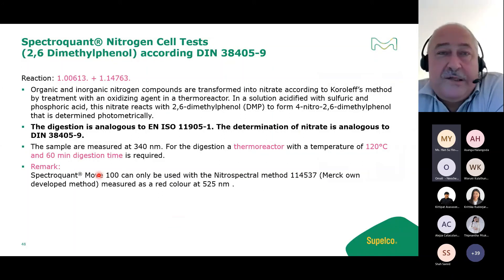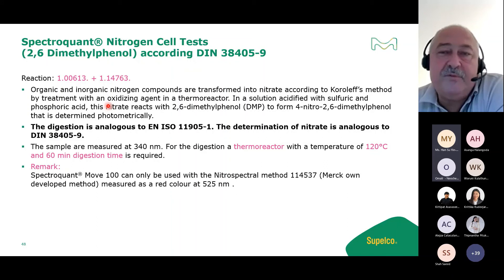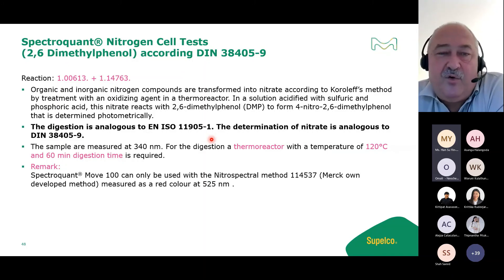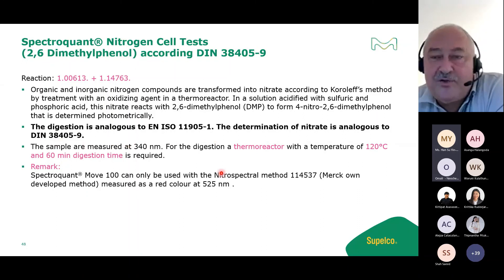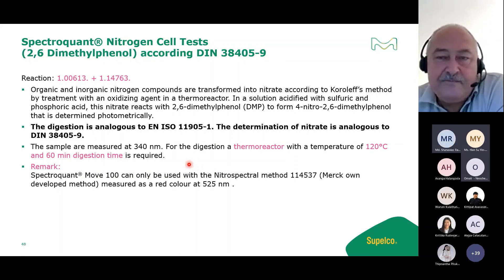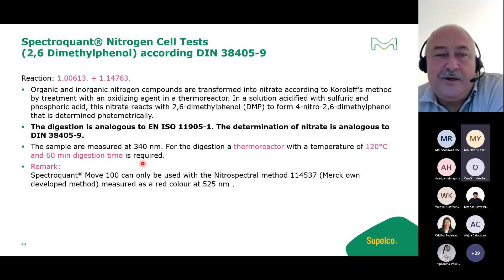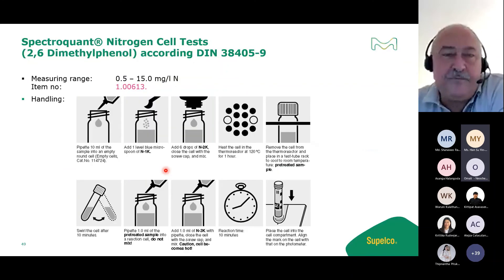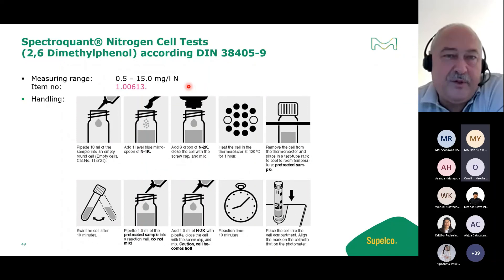For total nitrogen measurement, two test kits use the 2,6-dimethylphenol method. Digestion follows ISO 11905 part one, and nitrate measurement follows the German DIN standard. Digestion conditions are 120°C for 60 minutes. The measurement range of 0.5 to 15.0 mg/L is typical for wastewater treatment plant outlet measurement and is very easy to handle.